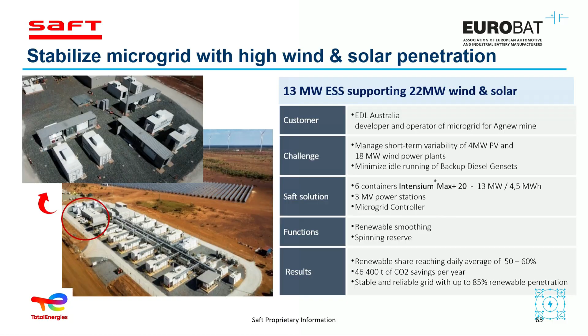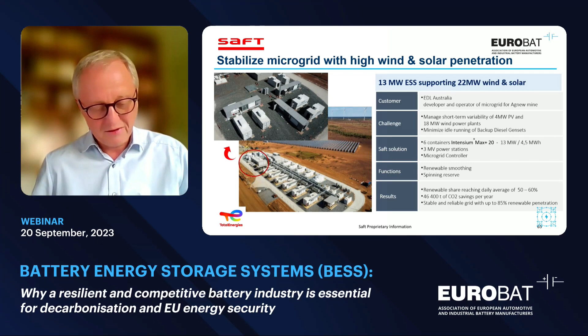The energy storage site is at the edge, consisting of lithium-ion battery containers provided by Saft. This is a 13 megawatt system, quite powerful, but only 4.5 megawatt hours, so small in energy terms. That's because the battery provides spinning reserves — balancing power to compensate for the variability of the wind and solar plant and stabilize grid frequency. This prevents the thermal engines from running idle and consuming power for nothing.